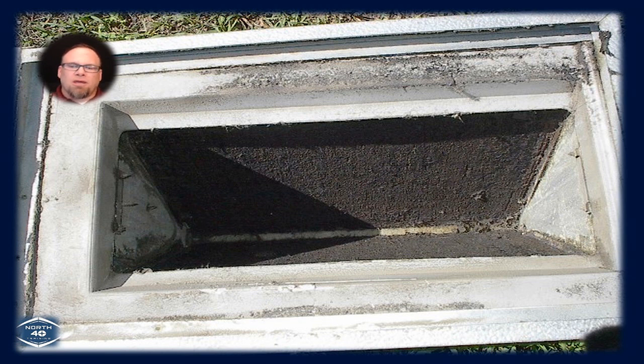So what they did is they go out there and they strap up the plenum with wire, so that way it stays in place as they pull out the furnace underneath. And rather than just stick your head under there and look up to see whether or not that coil has stuff that you could clean out of it while it's now wide open, they didn't do that. They got ahead of themselves and moved much more quickly than they should. And instead of finding this mess, what they actually did is just shove the new furnace under there, left that coil where it is, didn't check it out, built the plenum down to the top of the furnace, and then ran the furnace. Couldn't figure out why it tripped limit.